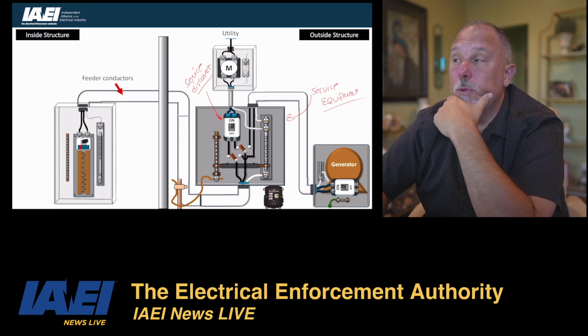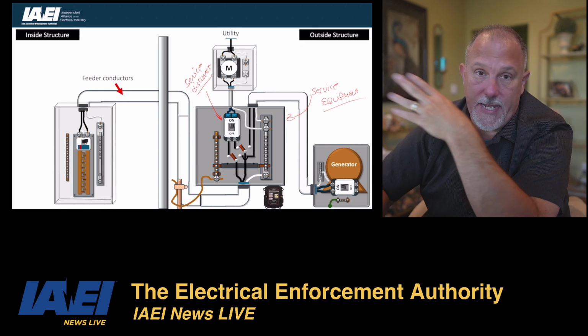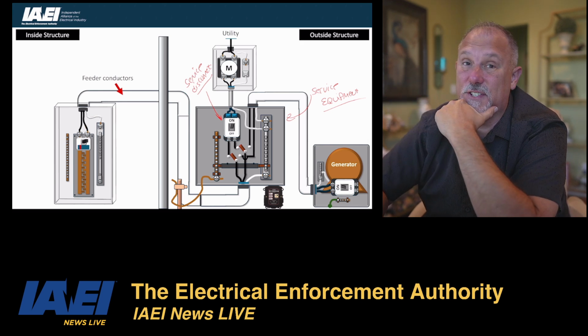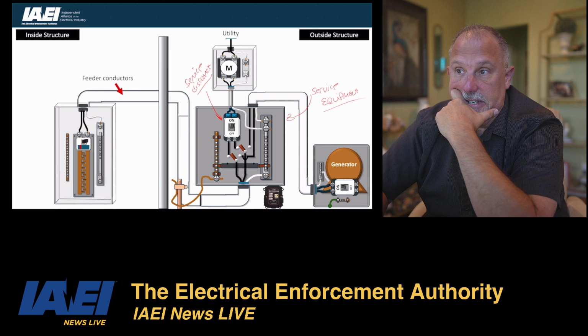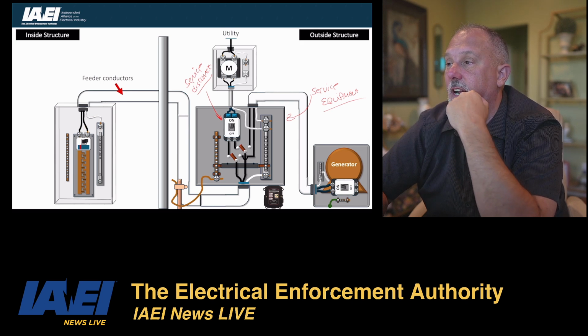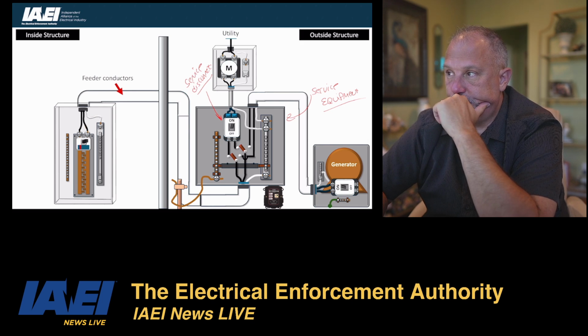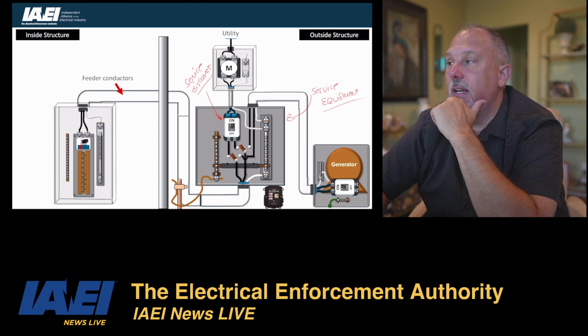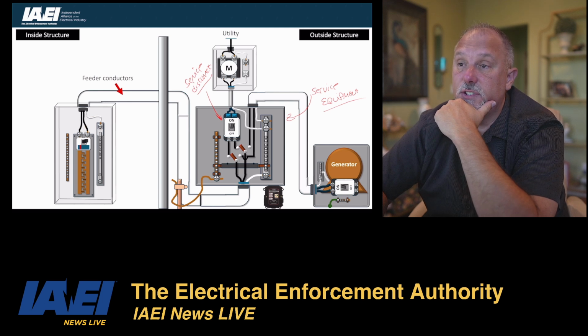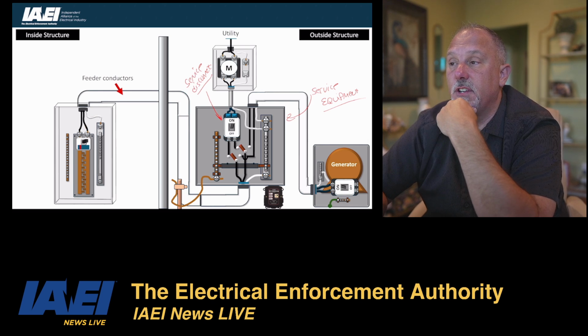Now, one of the changes I was going to make, and I still have it in there, and again, all of this is fluid up until August 28th. Conductors used to supply emergency systems, circuits for standby power systems, fire pump equipment, and fire sprinkler alarms. If provided with, and what it said was service equipment, I was going to change that to say, if provided with the equipment listed as suitable for use as service equipment and installed in accordance with the requirements for service entrance conductors.